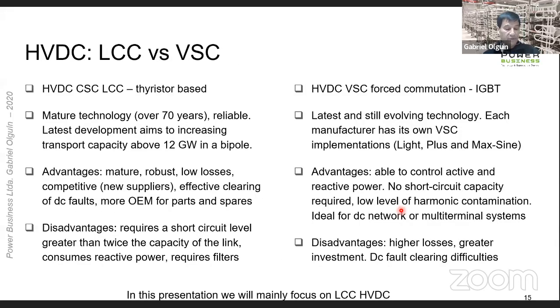Here you have a comparison of LCC and VSC for HVDC. LCC uses thyristor valves, while VSC uses IGBTs. LCC is a more mature HVDC converter technology, with the latest development aimed at increasing converter and transmission capacity above 12 gigawatts and 3,500 kilometers in a single bipolar link. LCC advantages are its robustness, low losses, competitive thanks to new OEM suppliers, and ideal for overhead transmission lines because of the effectiveness in clearing DC faults.